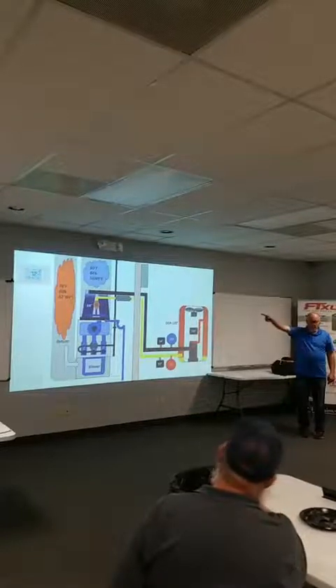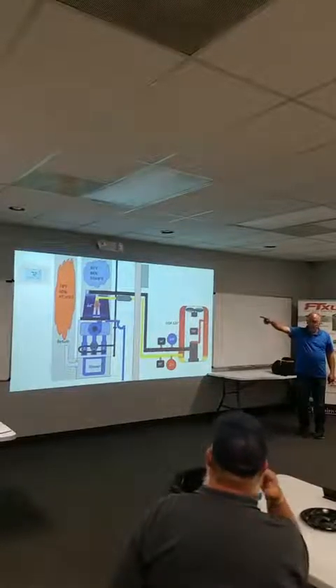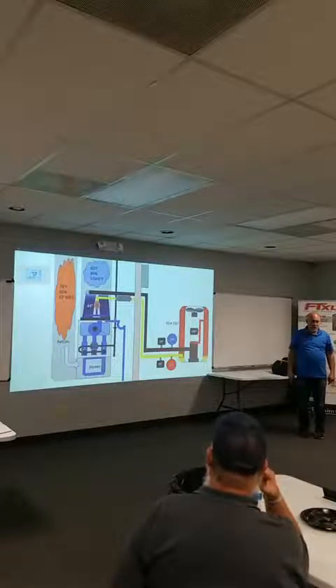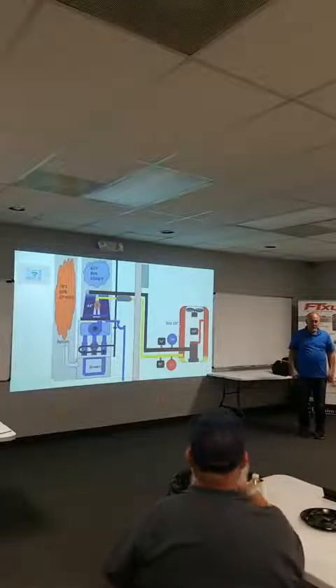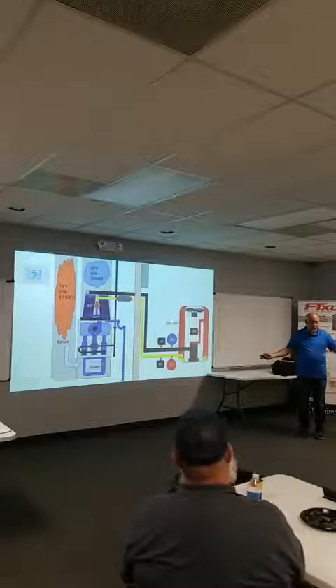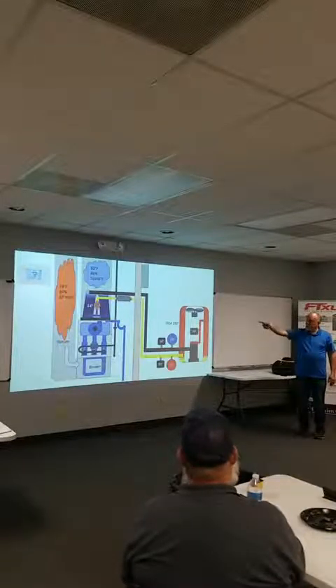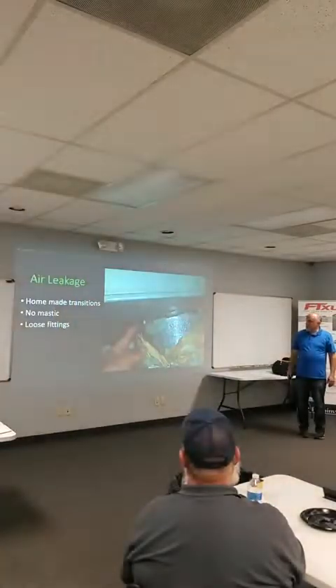Whatever the thermostat temperature, if this is 72 at the thermostat, it should say 72 degrees in the return air, right? It should be exactly the same temperature, right? If it's hotter, that means you're getting duct leakage from somewhere, right? That's gonna erode your system operation.